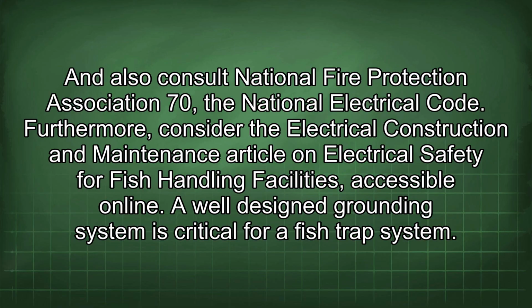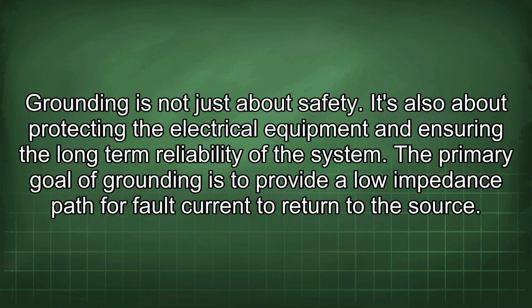A well-designed grounding system is critical for a fish trap system. Grounding is not just about safety. It's also about protecting the electrical equipment and ensuring the long-term reliability of the system. The primary goal of grounding is to provide a low impedance path for fault current to return to the source.